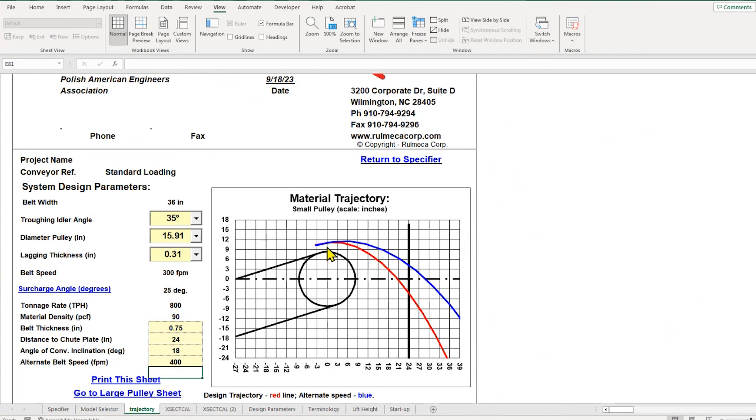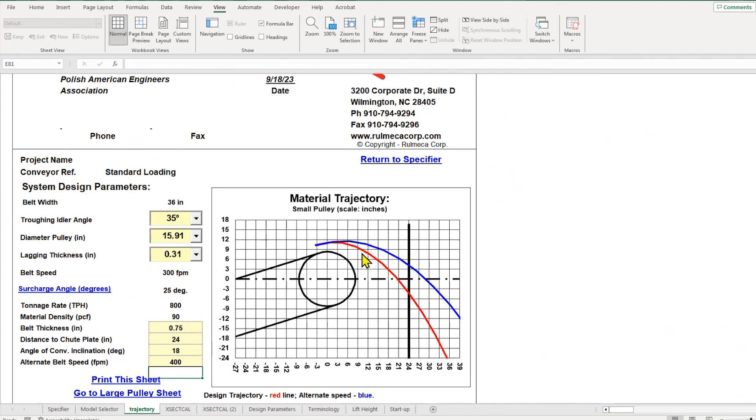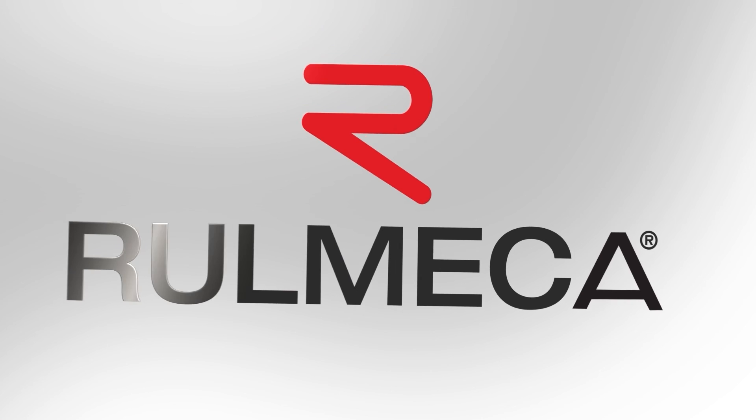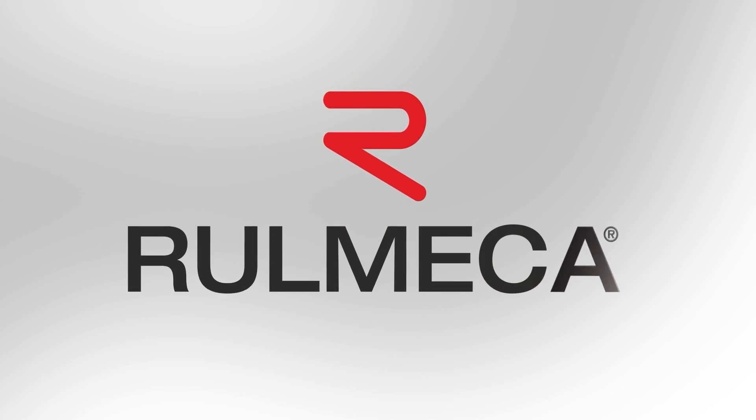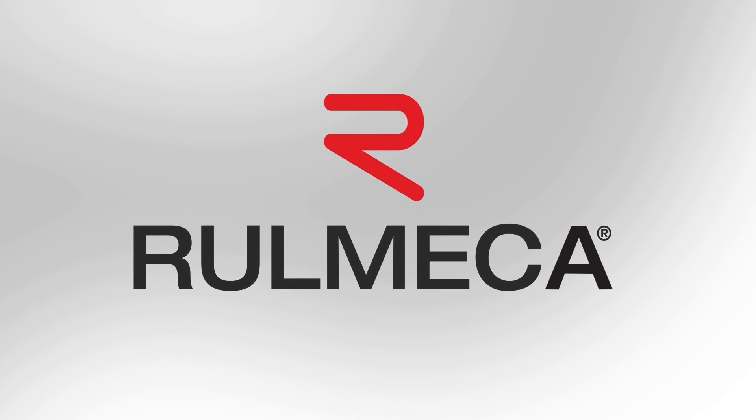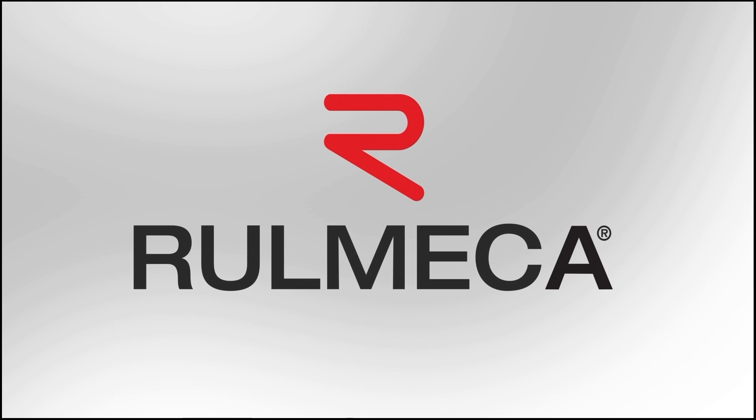On the other hand, our design belt speed—we selected 300 feet per minute—falls below the horizontal center line, and the material should flow freely through.